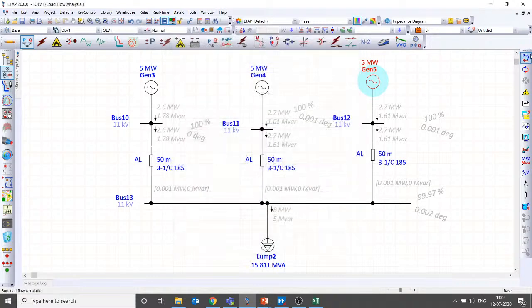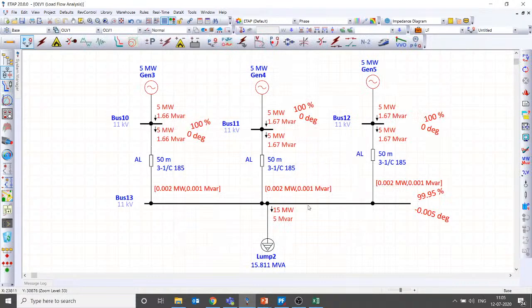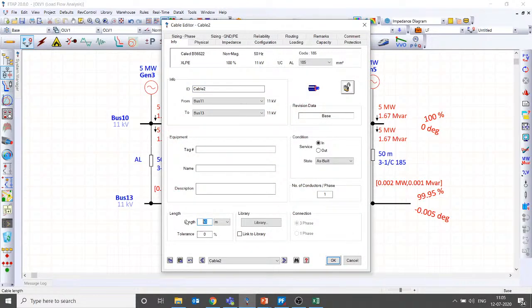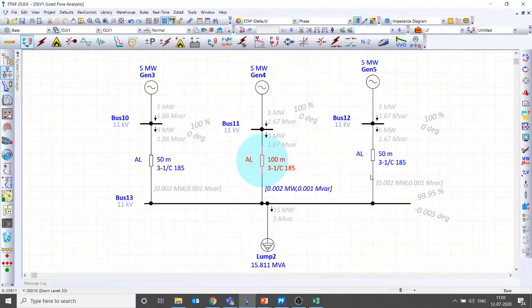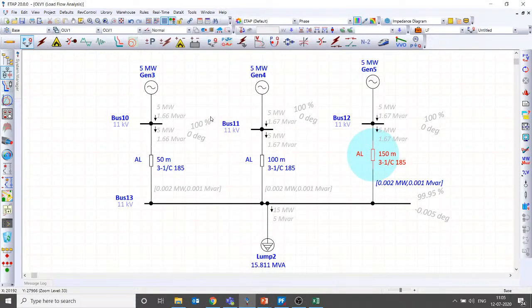So now the demand is 5 megawatt each, 15 megawatt, so it seems like equal sharing. But I'm just doing a small change. Assume the cable length is not 50 meters. I am taking 100 meters, and I'm taking the other cable length as 150 meters. Previously this 15 megawatt demand was equally shared by all the generators, 5 megawatt each. Now I have not changed anything in the generator parameters. I have just changed the cable length between the generator and the switchboard. Look at the results.